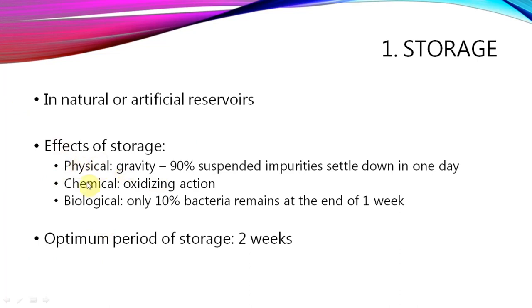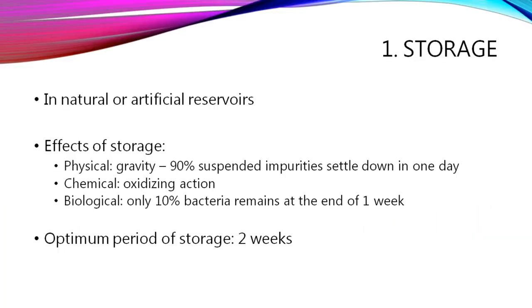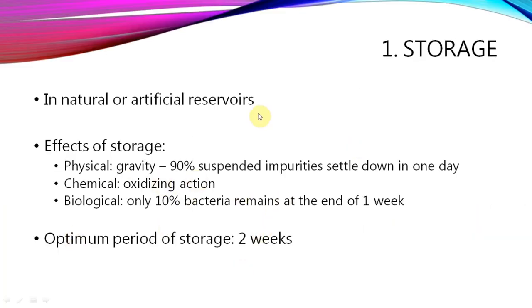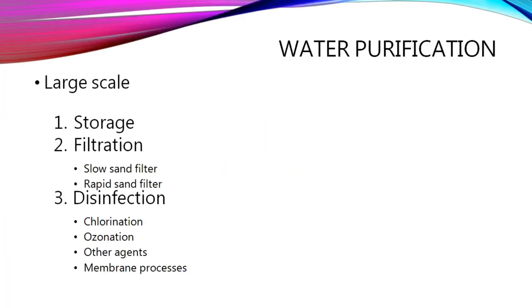For storage, we can use natural or artificial reservoirs. The effect of storage involves physical, chemical, and biological action. Physically, 90% of impurities will settle and there will be oxidizing action. Biologically, only 10% of bacteria remain at the end of one week. The optimum storage period is two weeks - if kept more than two weeks, algae production becomes a problem. So the maximum storage period is two weeks.